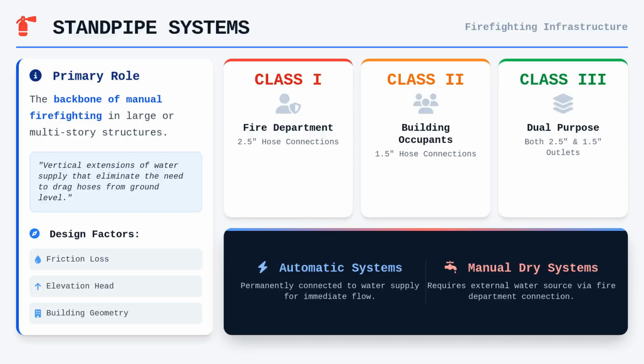To understand standpipe systems, we first have to appreciate their primary role as the backbone of manual firefighting in large or multi-story structures. A standpipe network is essentially a vertical extension of a building's water supply, designed to provide water at strategic locations to allow firefighters to attack a fire without needing to drag hoses from the ground level. We categorize these systems into three main classes, starting with Class 1, which is intended for utilization by trained fire department personnel and requires 2.5-inch hose connections. Class 2 systems are designed for use by building occupants and typically utilize smaller 1.5-inch hoses, whereas Class 3 systems serve a dual purpose by providing both the higher flow capabilities of a Class 1 system and the smaller hose connections for immediate, albeit limited, occupant response.